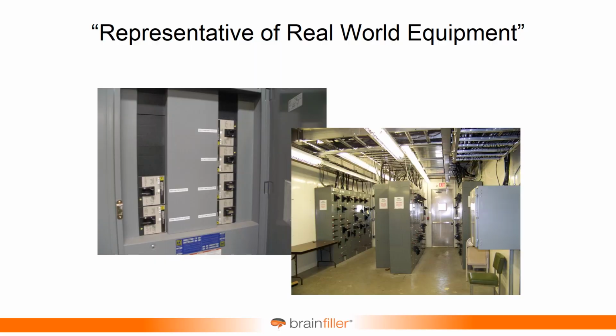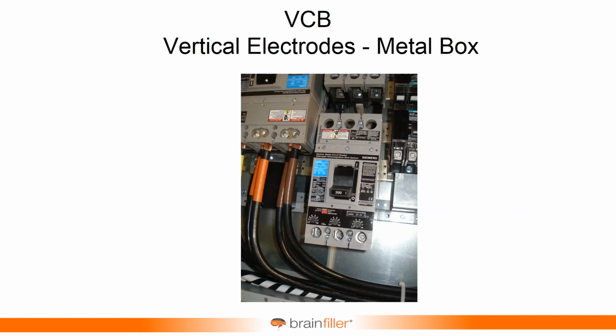So the idea of having these different configurations is so that you have more flexibility if you want to be more creative in modeling the different types of equipment. For example, the vertical electrodes in a box is just, I'll call it a run-of-the-mill arc flash, the way we've been treating it so far, where you have an arc flash in an enclosure, and it just comes out of the enclosure. And that's the way that we've been handling this since 2002, and pretty effectively with good results.